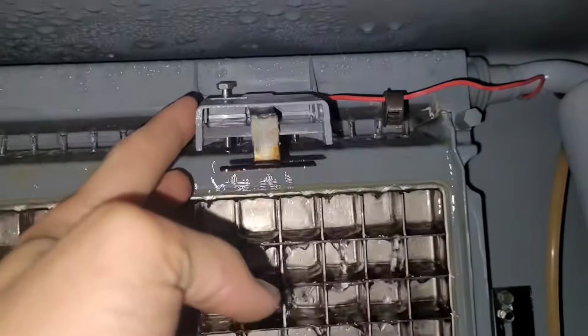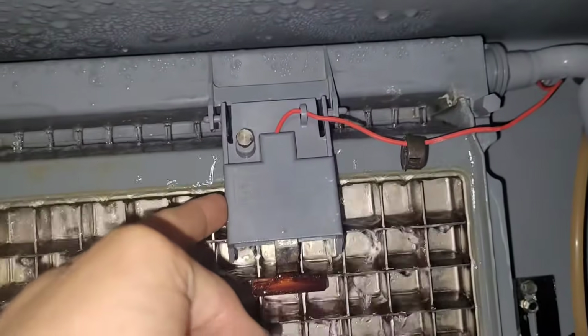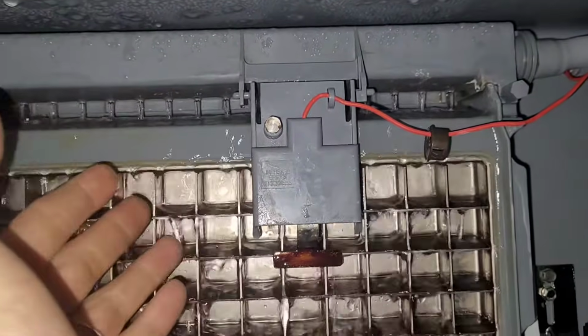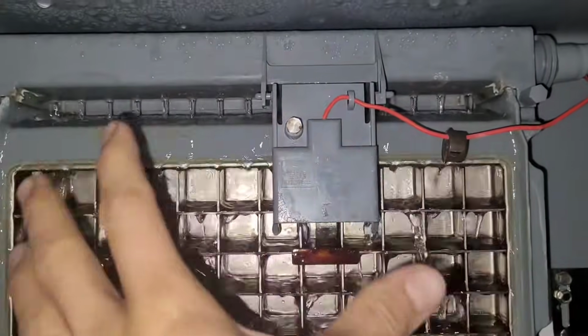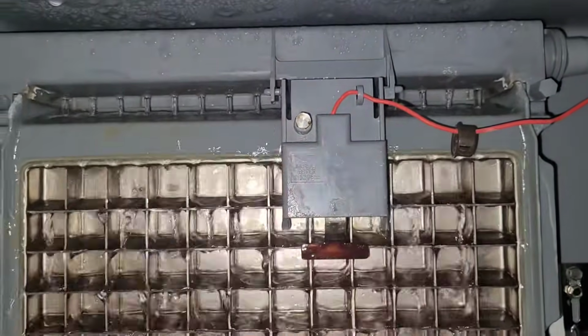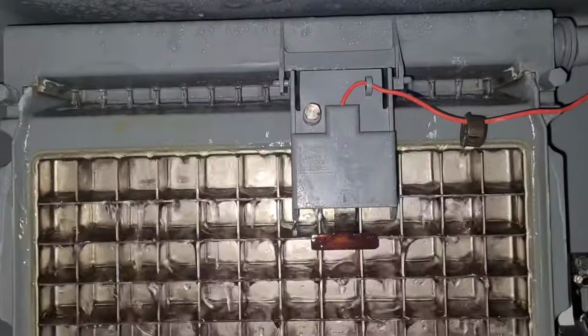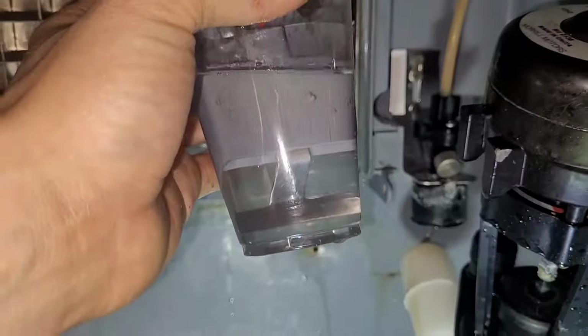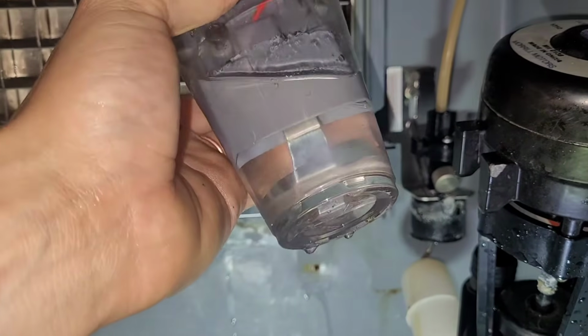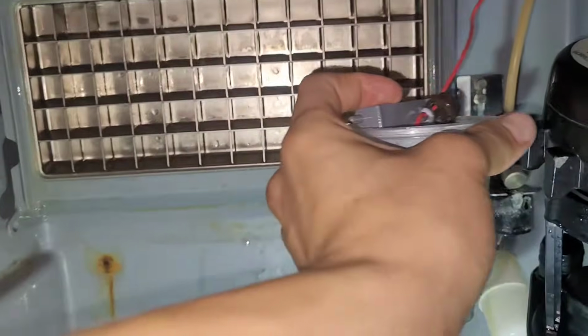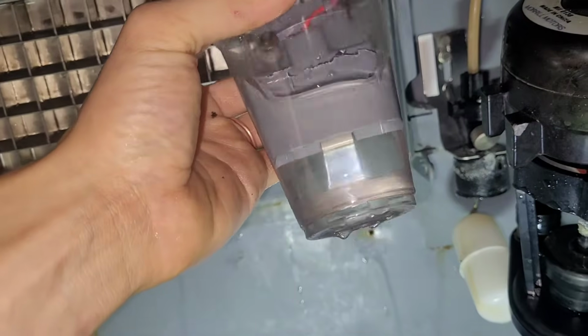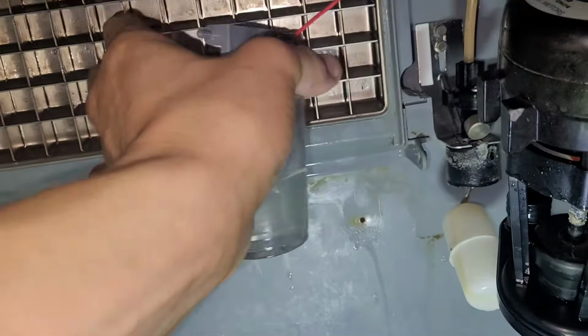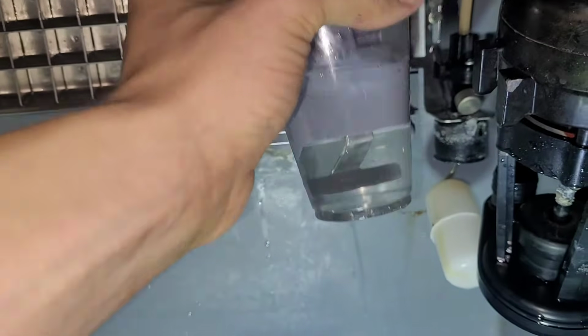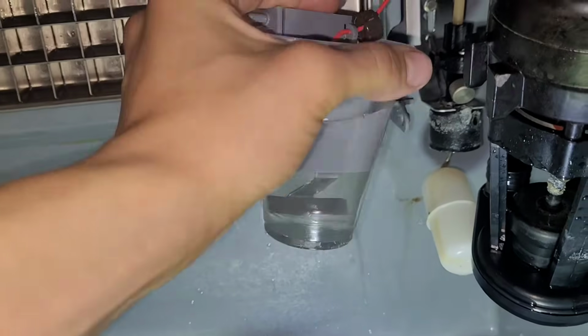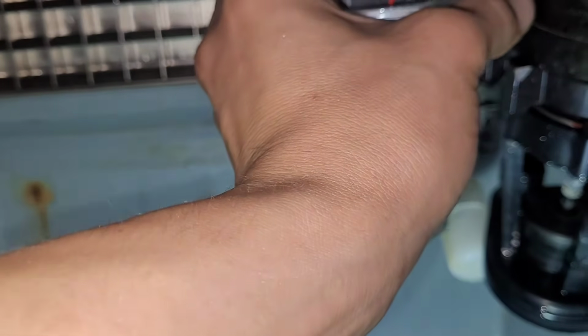this whole thing needs to be cleaned and descaled so that it's not sensing just through the water some other way. So we're gonna pull it apart, clean it, make sure that it's all good to go that way, and then it probably will work good again. My go-to method is to soak this in a cup of vinegar while I clean all the other components, which I've already done, and now I can basically start reassembling. And then we'll use this same cup of vinegar to kind of rinse everything down once, kills off the bacteria, gets rid of some of the lime scale, and then we'll flush it out with fresh water.